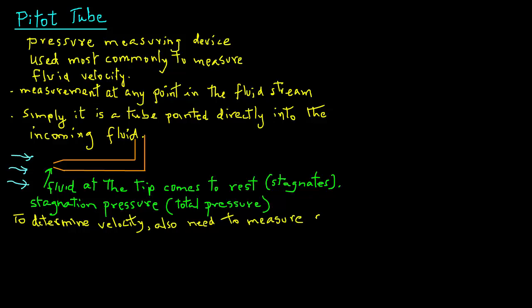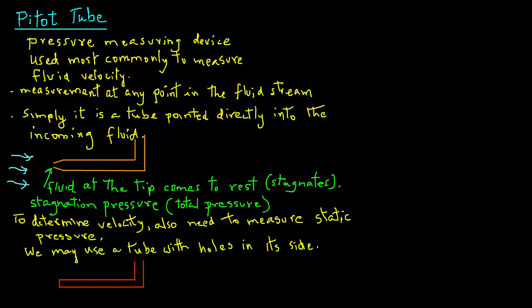Now, to measure the velocity of the fluid, we also need to measure what is called the static pressure. For static pressure, we could use a tube, as shown in this diagram, where the tube has got holes drilled on the side of the tube, and the front end of the tube, the tip of the tube, is closed. The side holes are the ones that will allow us to measure static pressure at that location.